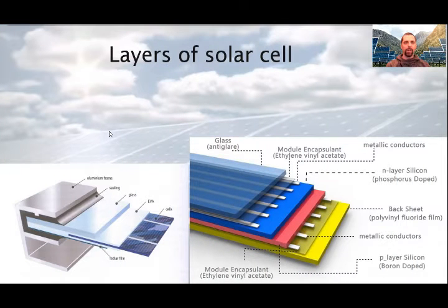After we learned about the operation of solar cells, now let's see its structure. The blue and red ones are silicon layers, the N and P type layers. These we all know already. Both sides have metallic conductors. Above them, you see the glass. The front glass sheet protects the solar cell from the weather and impacts from hail or airborne debris. The glass is typically high-strength tempered glass, which is 3-4 mm thick, and is designed to resist mechanical loads and extreme temperature changes. This type of glass is much safer than standard glass.